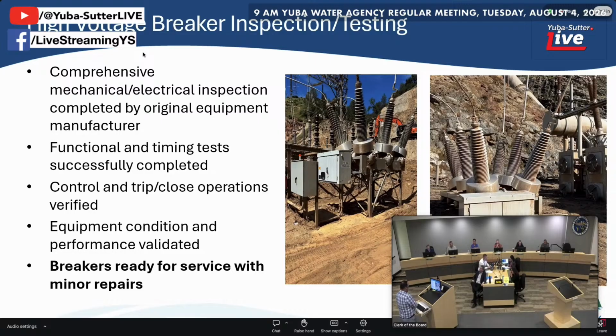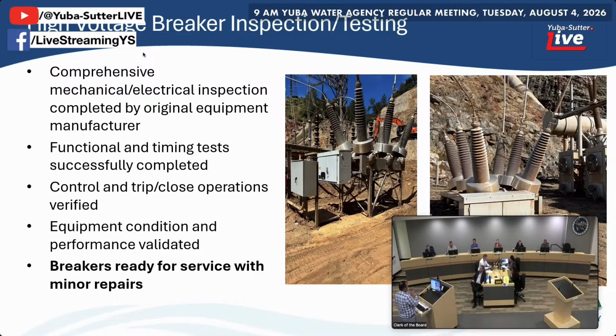These are the final contact point between the GSUs, the generator step-up transformers, and the transmission line. This is a protection device: in case a fault or grounding happens, this device is supposed to trip and disconnect everything. So we tested this, doing complete comprehensive testing, electrical, mechanical, and functional testing on the bushings, contacts, and everything.